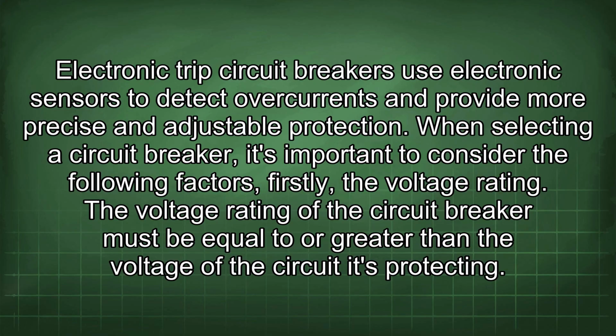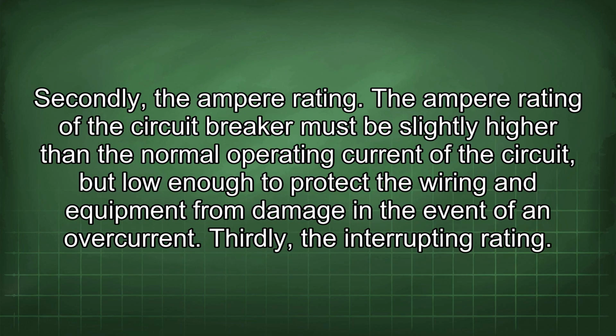When selecting a circuit breaker, it's important to consider the following factors. Firstly, the voltage rating. The voltage rating of the circuit breaker must be equal to or greater than the voltage of the circuit it's protecting. Secondly, the ampere rating. The ampere rating of the circuit breaker must be slightly higher than the normal operating current of the circuit, but low enough to protect the wiring and equipment from damage in the event of an overcurrent.